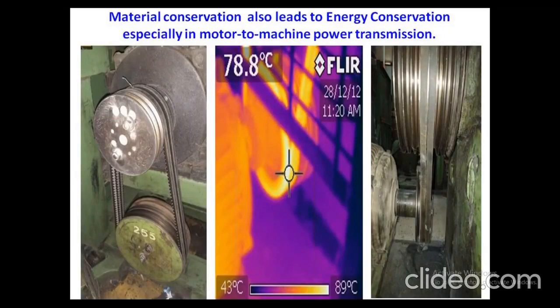Coming to the motors, motor to machine, the power transmission, all the TFOs, the twisting machines, the old generation, I am talking about the old machines, and I am talking about the new machines also. You can see so much weightage is given to the motor pulley and machine pulley, just by replacing. It is not only material conservation, it is also going for pulley resizing. As an energy auditor, we have suggested they go for cogged belts, but a cogged belt on the heaviest pulley is totally irrelevant. We have to resize the pulley, and automatically this also brings down the energy consumption. This also gives energy saving.